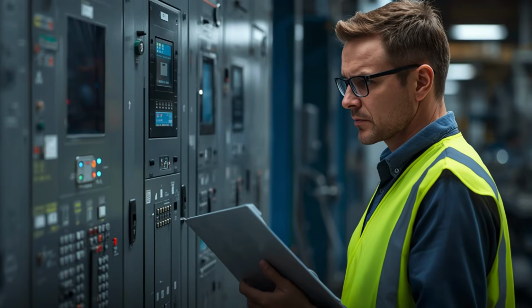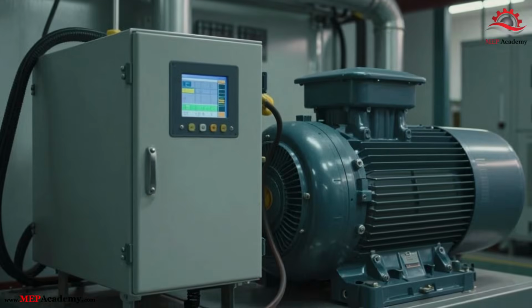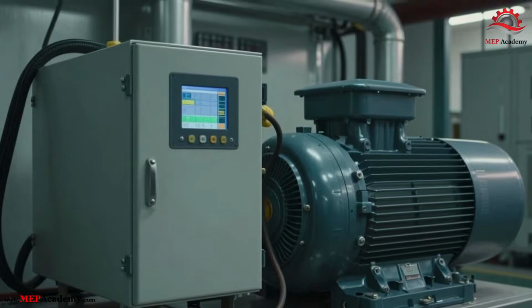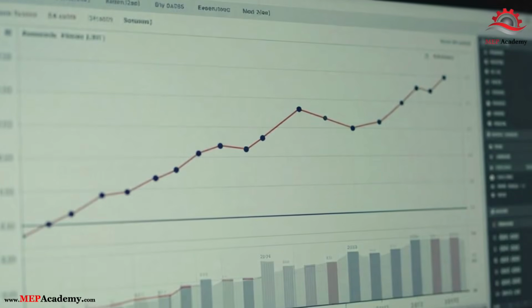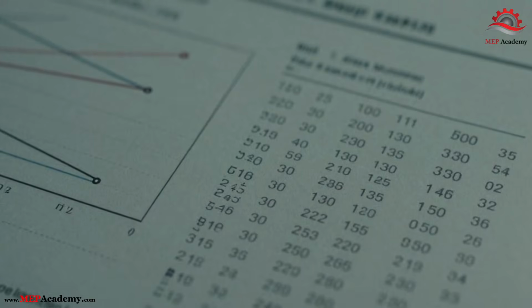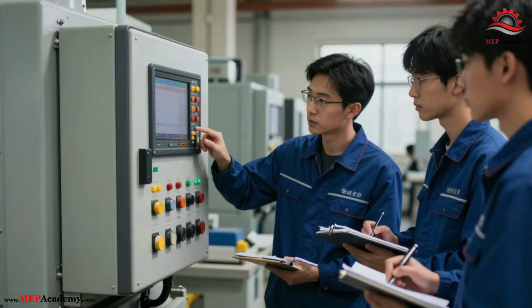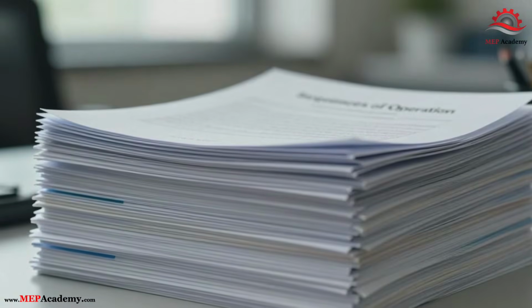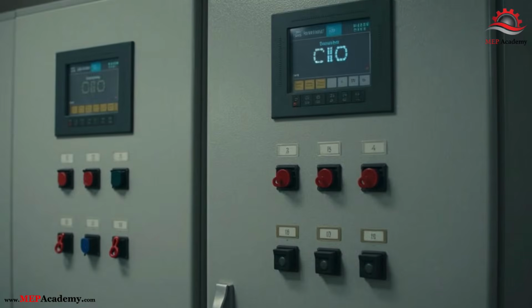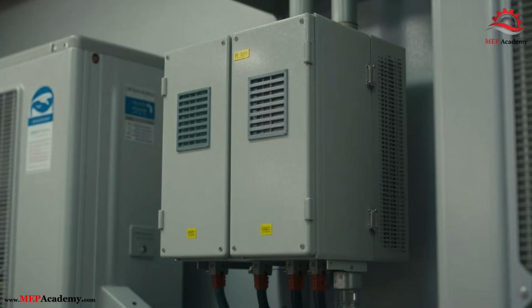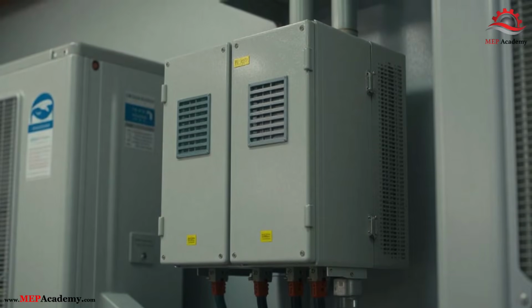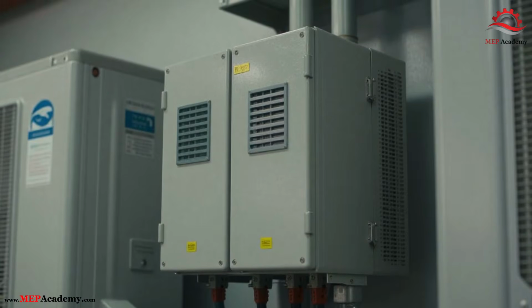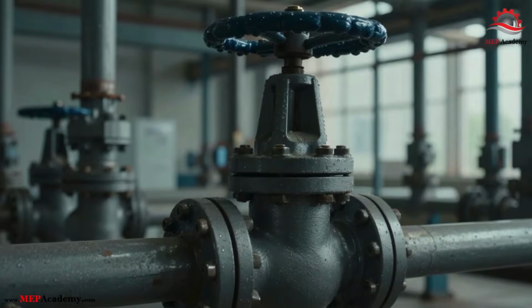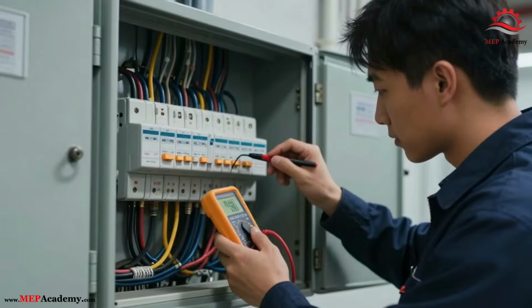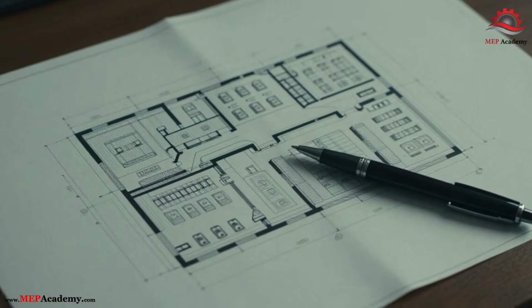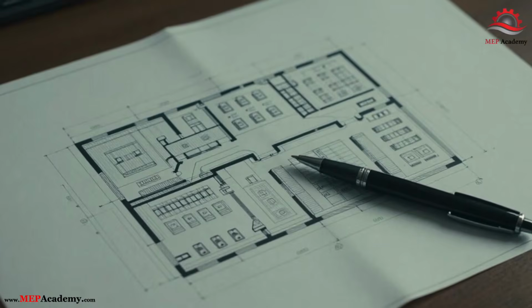Section 7. Commissioning and turnover. A successful VFD retrofit includes trend logs at multiple load conditions, set point documentation, operator training, written sequences of operation. If you don't lock this in at turnover, the system will revert. VFD retrofits can absolutely deliver energy savings, but only when the mechanical system can handle turndown, the electrical system is evaluated properly, the control strategy is designed, not improvised.